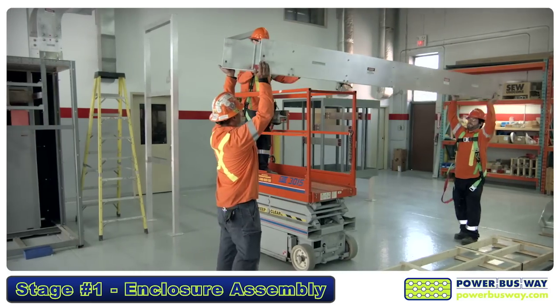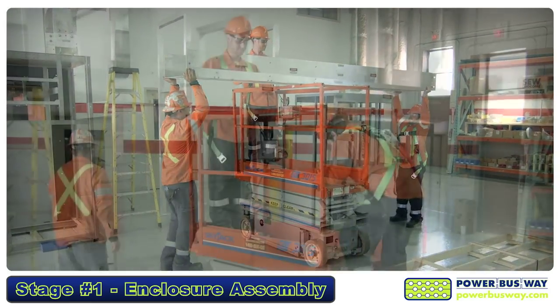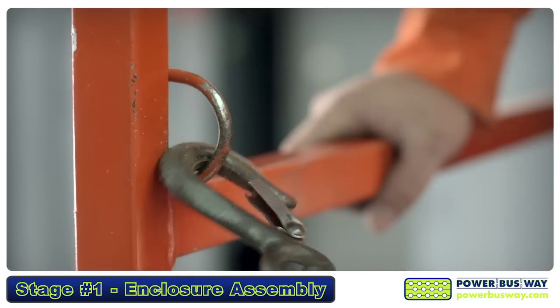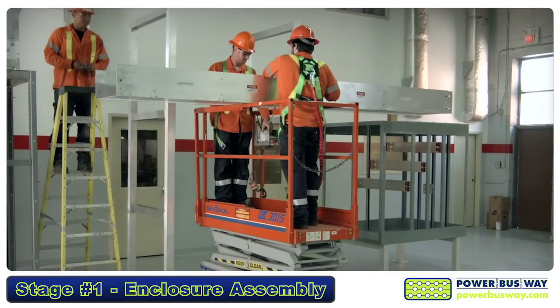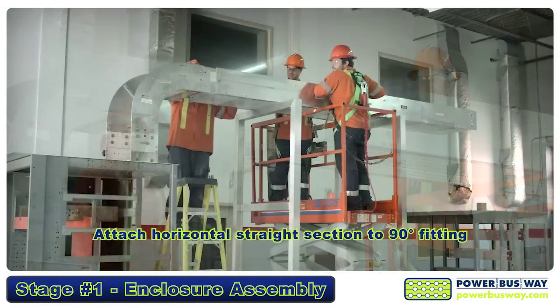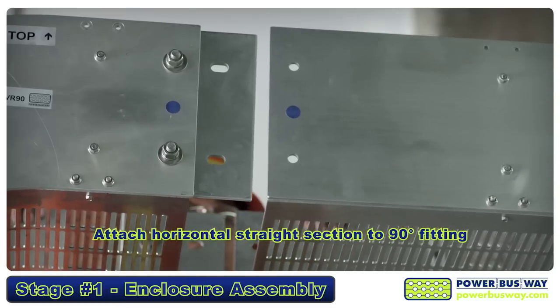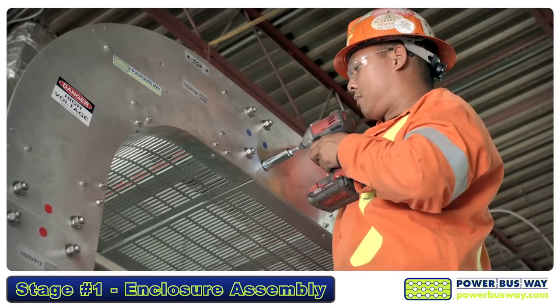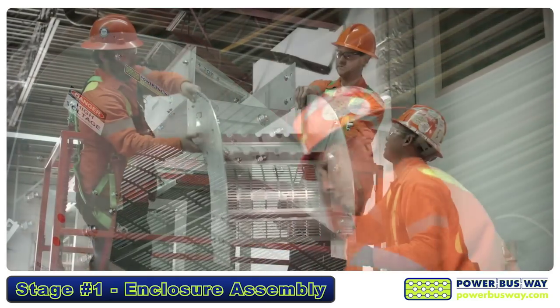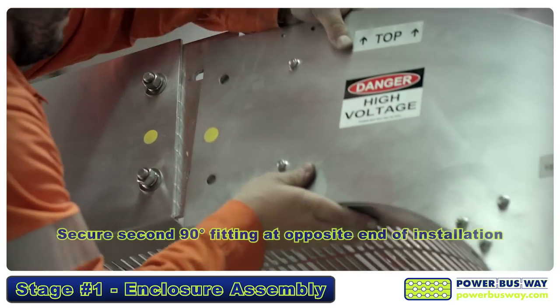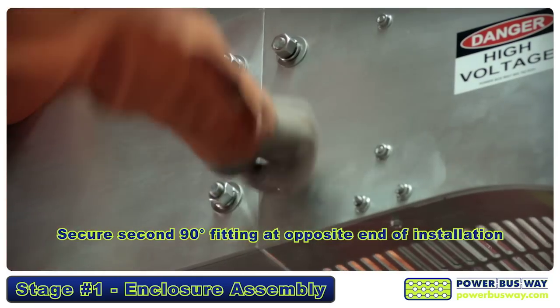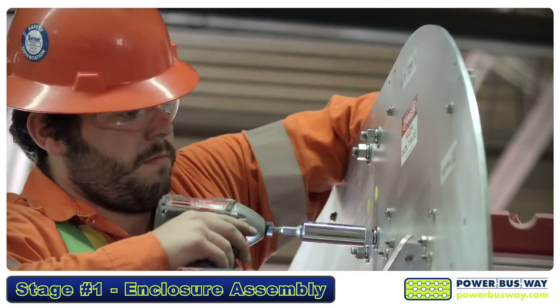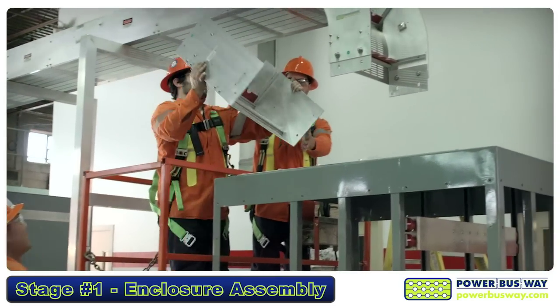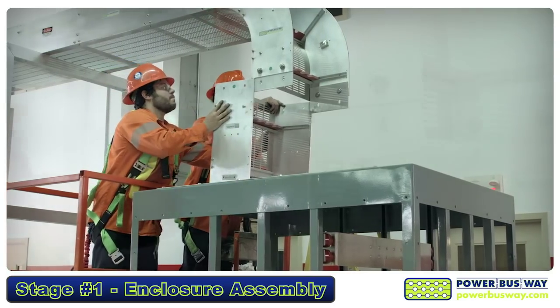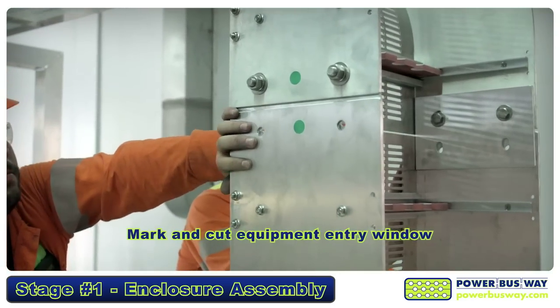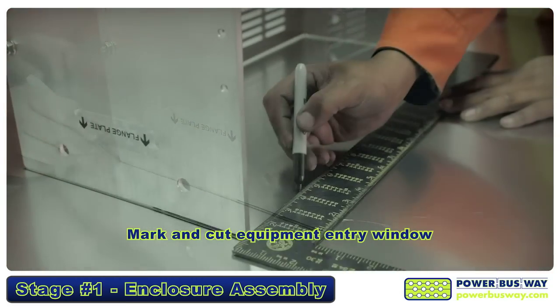Next up, attach the horizontal straight section to the vertical 90-degree fitting. Be sure to follow all lift safety guidelines when performing any elevated assembly. Align the horizontal straight section to the vertical 90-degree fitting and slide into place. Secure properly before continuing. At the opposite end, immediately above the second termination compartment, position and fasten the remaining vertical 90-degree fitting. Then, using the second vertical straight section, you will be able to determine the placement of the final equipment entry window. Slide the section firmly into place and mark the window location before proceeding.